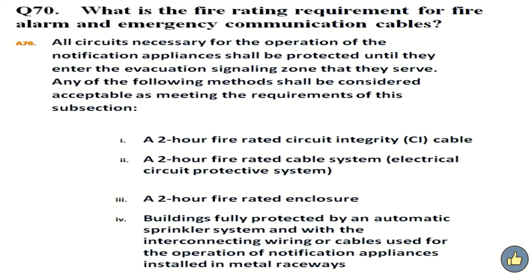What is the fire rating requirement for fire alarm and emergency communication cables? Answer. All circuits necessary for the operation of the notification appliances shall be protected until they enter the evacuation signaling zone that they serve. Any of the following methods shall be considered acceptable as meeting the requirements of this subsection. 1. A 2-hour fire rated circuit integrity (CI) cable. Number 2. A 2-hour fire rated cable system, electrical circuit protective system. Number 3. A 2-hour fire rated enclosure. Number 4. Buildings fully protected by an automatic sprinkler system and with the interconnecting wiring or cables used for the operation of notification appliances installed in metal raceways.